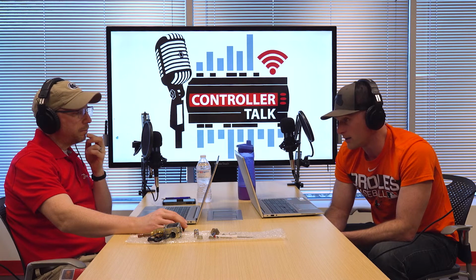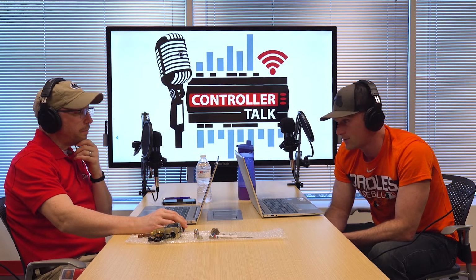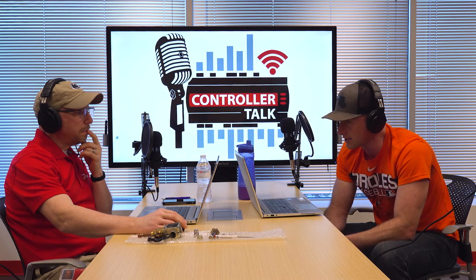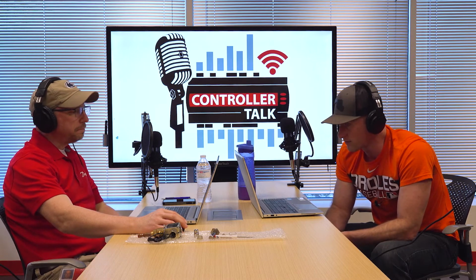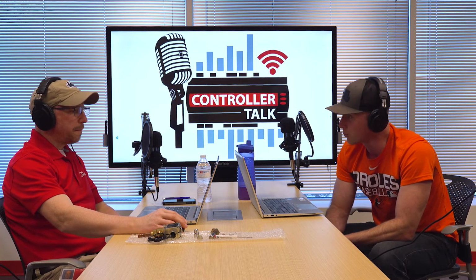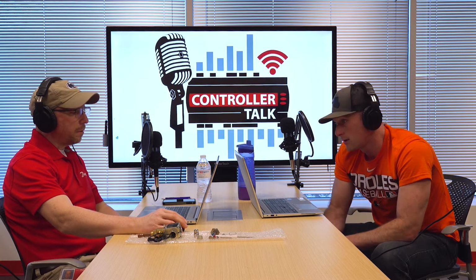And then we want to make sure the case isn't iced up. So, I mean, a pretty easy check there, right? We can see if it's pulling down slower and slower over time. If you look at the history in the system manager that's tied to all this, if one is being used, then that might give you a feel for the fact that slowly over time that ice buildup's getting worse and worse, and that's why we're not pulling down as fast.